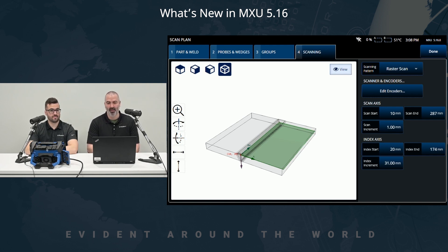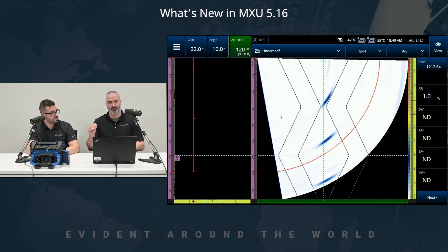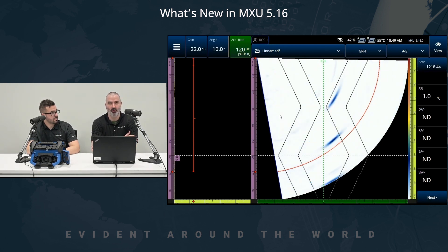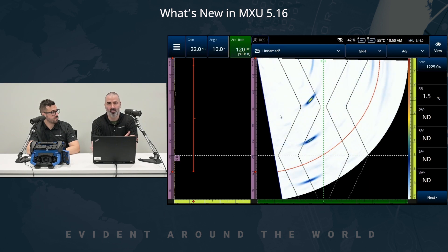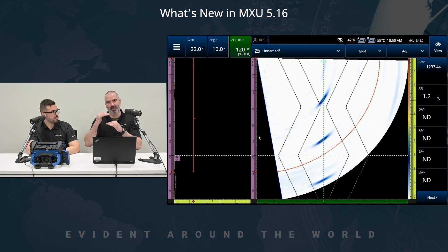Now let's jump into the TCG calibration for phased array inspection. What I have in front of me is a setup done with a dual matrix array probe and a couple of side drill holes. Typically with a TCG calibration, you want to collect the amplitude of a reflector from every beam or angle and normalize that amplitude to a reference level. But in a case where it's impossible to normalize both the minimum and maximum angles with the same reflector, we're in a bit of a pickle. So with MXU 5.16, we added the ability to not only gate the reflector depth-wise but also add index limiters.